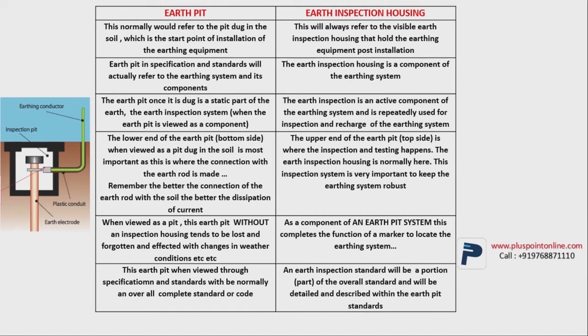Furthermore, once you dig a hole in the ground, your earth pit is formed, which is a static part of the earth, but earth inspection housing is an active component. Once the earthing is done, you won't dig up the hole again, but we'll have to keep checking the earthing system every 2 to 4 months. Therefore, you will have to keep opening the earth inspection housing to inspect the earthing system. Allow me to go into more detail.